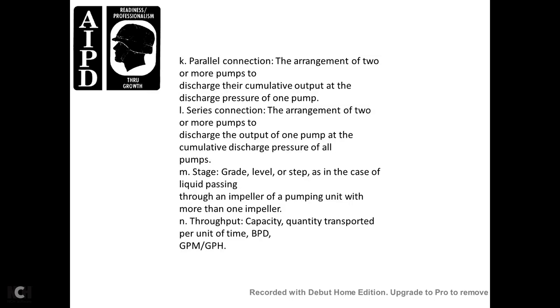In a series connection, two or more pumps are arranged so that the discharge output of one pump feeds into the next, combining the discharge pressure of all pumps. A stage is a grade, level, step, or — as in the case of liquid passing through an impeller — a pumping unit with more than one impeller. Throughput is the capacity or quantity transported per unit of time, expressed in barrels per day, gallons per minute, or gallons per hour.